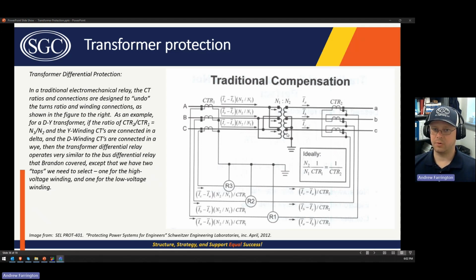But you also have to consider the winding differences for this transformer. So this is a delta Y transformer. So what would historically be done for a delta Y transformer is to connect the delta side of the transformer would have CTs connected in a Y configuration, and then the Y side of the transformer would have CTs that are connected in a delta configuration. And the connections of these CTs is important because you want to connect the polarity dots such that they undo the phase shift of the transformer. So you need to pay attention to that.